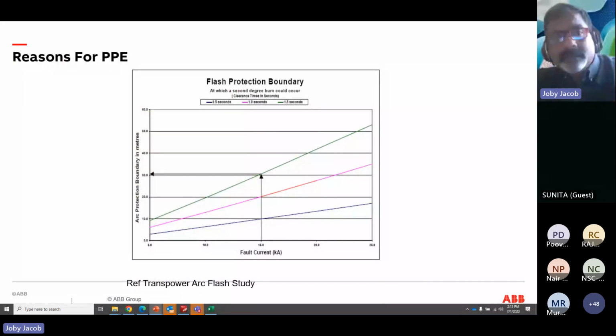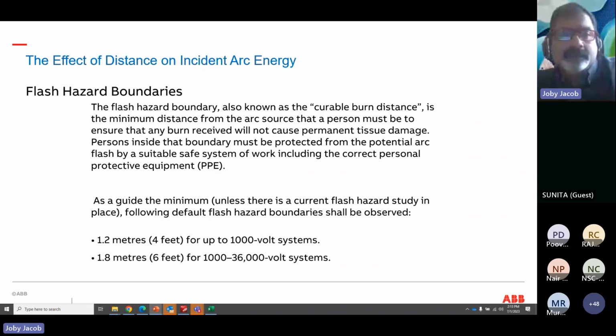Again, a little bit on the reasons for PPE. As the fault current increases, the arc flash boundary also increases. So this is a rough calculation based upon NFPA 70E, the American standard. So 1.2 meters, 4 feet, for anything up to 1000 volt systems, and 1.8 meters, up to 6 feet, up to 36 kV systems. It may not be 100% accurate. This is based upon the experience of the calculations they have done.